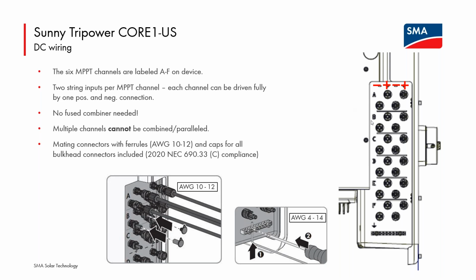And below all of the 6 tracking channel connectors, you have a small DC equipment ground bus bar there for connection. And you can see everything labeled A through F here. As I said, you can combine 2 strings together to bring a single positive and negative back to drive each of the 6 tracking channels. The one thing you cannot do with the CORE1 is parallel across these 6 tracking channels. So a fully loaded inverter, at a minimum, you would have 6 positive and negative home runs coming back to the inverter, and maybe up to 12. So you cannot parallel across these tracking channels. That is one of the very few things you can't do with the CORE1.